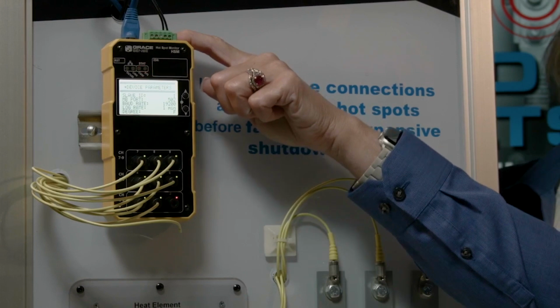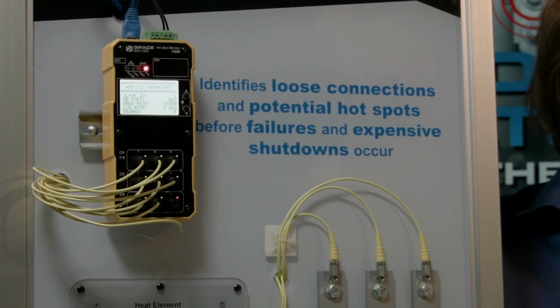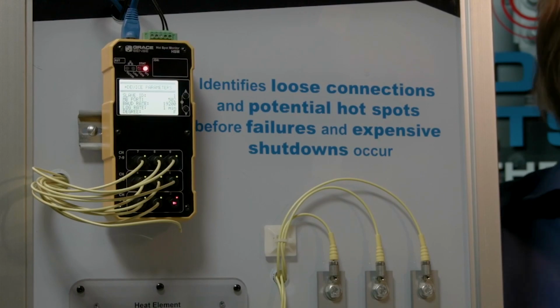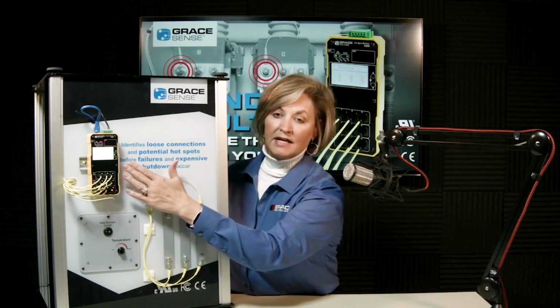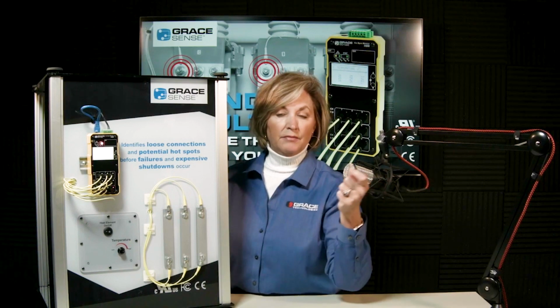And also it has an internal relay. This relay will close upon the temperature rise to the lowest level threshold that is set inside the product. The factory defaults are 90 and 105. So if any one of these points escalates to 90 degrees, it'll automatically close that relay and notify personnel either via a PLC, maybe even through a protective relay, for example, a horn or some other method by which to get the alarm notification to the appropriate personnel.